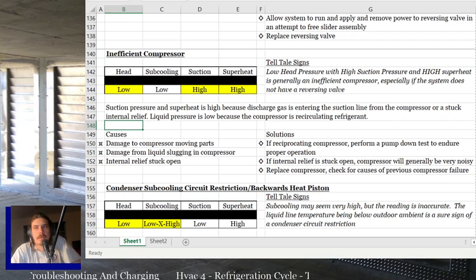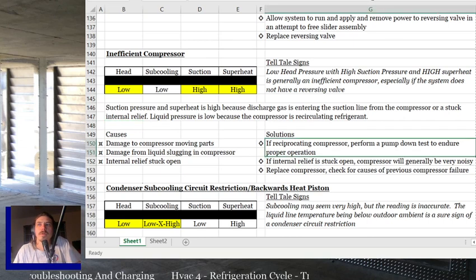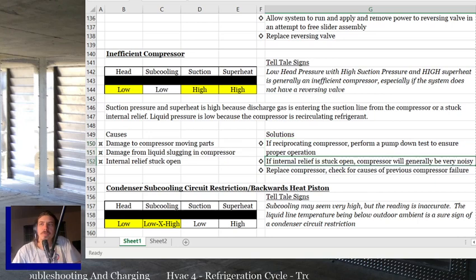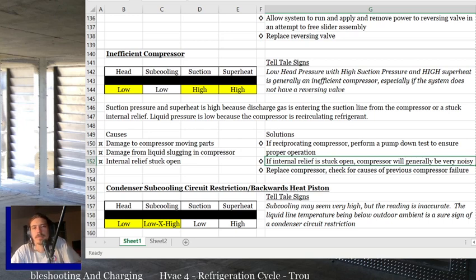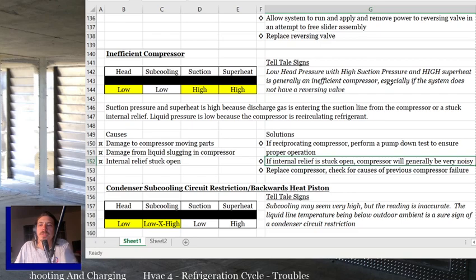If it's a reciprocating compressor, perform a pump down test to ensure proper operation. We'll talk about doing a pump down test at some point, but basically you just pump the system down and make sure it pumps down and holds a pump down. It's not that complicated. If the internal relief is stuck open, you'll usually hear it. The compressor is noisy as hell when that happens, so hopefully you'll be able to just notice it from the sound. But if not, you just diagnose it and replace the compressor, because either way it's an inefficient compressor. Replace the compressor, and check for causes of the previous compressor failure.